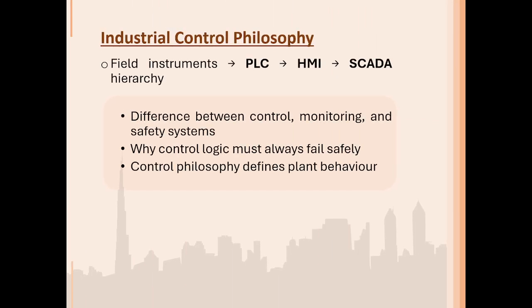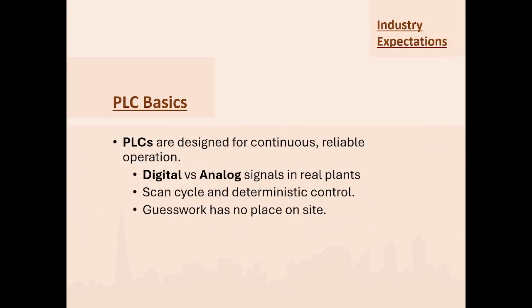Moving further to understanding industrial control philosophy. The control philosophy describes how a plant is intended to behave. It defines what is controlled automatically, what is only monitored, and what conditions will trigger protection or shutdown. The control philosophy also defines the difference between control systems and safety systems. A key principle is this: control logic must always fail safely. Now, applying this philosophy correctly, we must understand how PLCs actually work. So that takes us to the PLC basics.